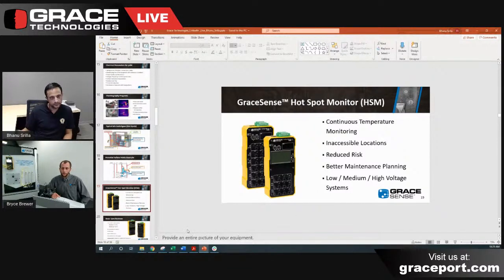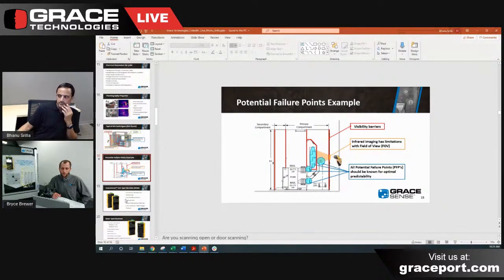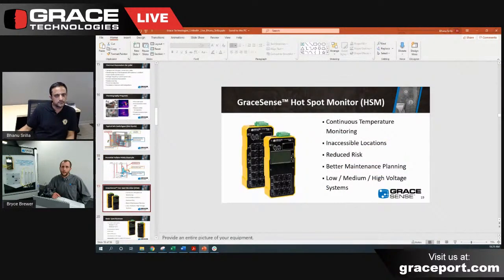Yeah, absolutely. One of the things Bhanu mentioned before was how this type of thermography needs to be done continually. You can't take a snapshot and know what happened between two scans, and it's very important to know what happens over that time. From this slide, you'll see the inaccessible locations again that Bhanu and I both mentioned, but reduced risk is a big thing, especially with open door thermography - that's a large risk. I'd encourage any employer needing to perform those to evaluate how necessary it is, and whether there's a better way to do it.